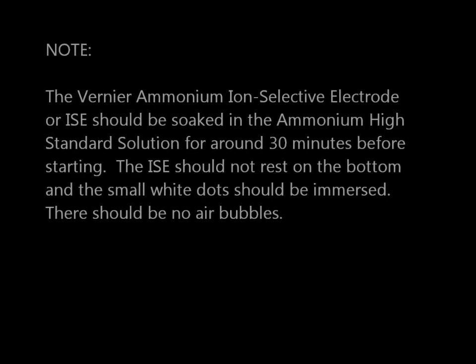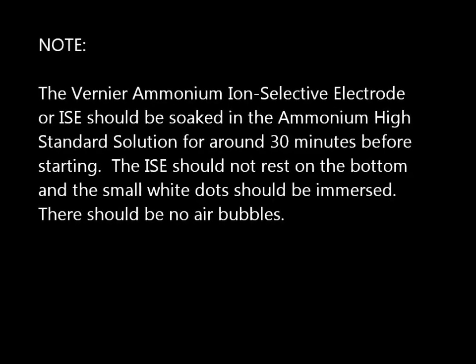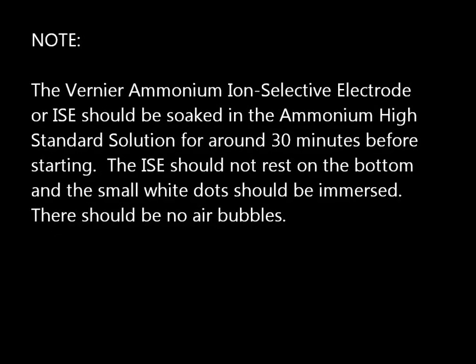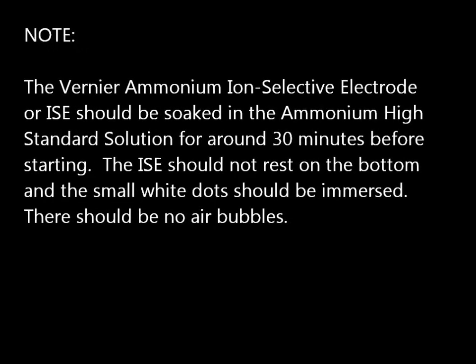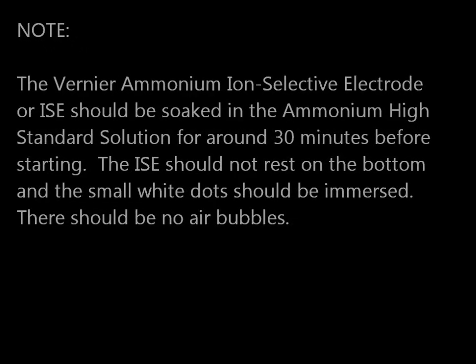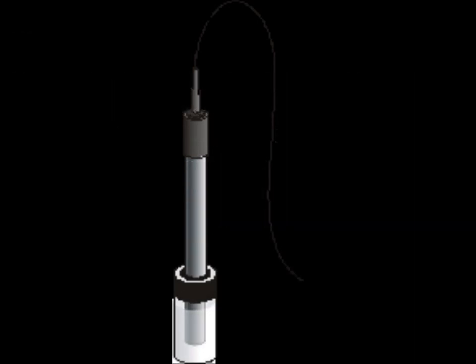Note: the Vernier ammonium ion selective electrode, or ISE, should be soaked in the ammonium high standard solution for around 30 minutes before starting. The ISE should not rest on the bottom, and the small white dot should be immersed. There should be no air bubbles.